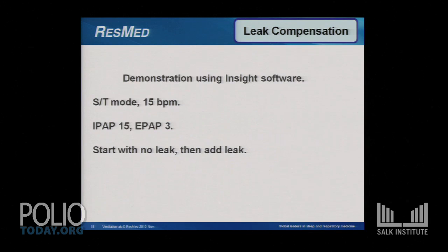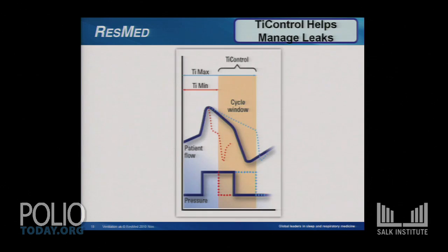So another thing I wanted to show you, an especially important feature on the ResMed products, is called TI control. And I think this is especially important for some of you folks that are prone to leaks or very short breaths. Now, TI control is typically manipulated by your respiratory therapist. Usually the physician does not order these settings, so it is important that your therapist be up to date on how to set TI control.